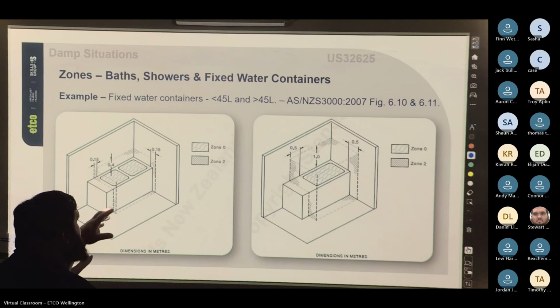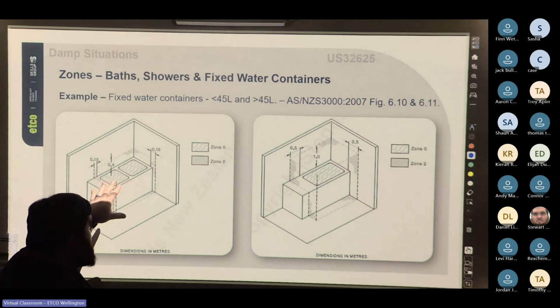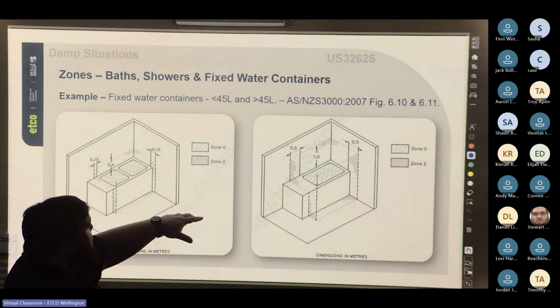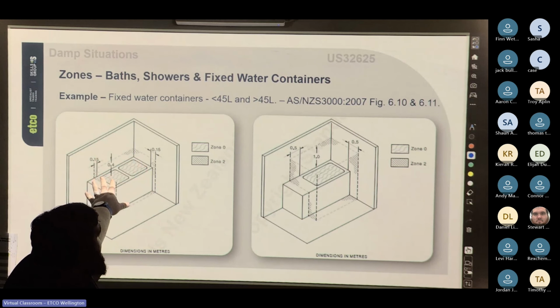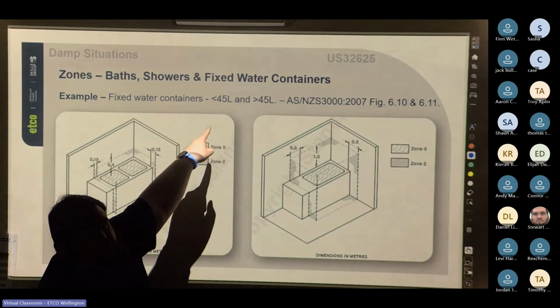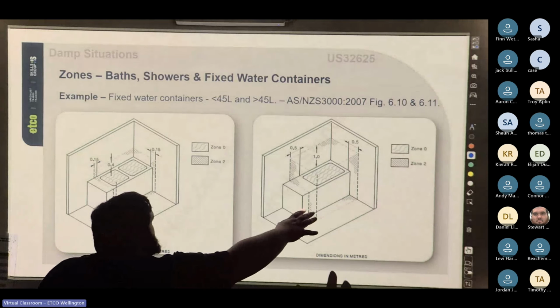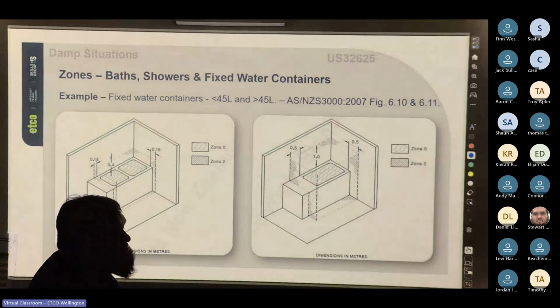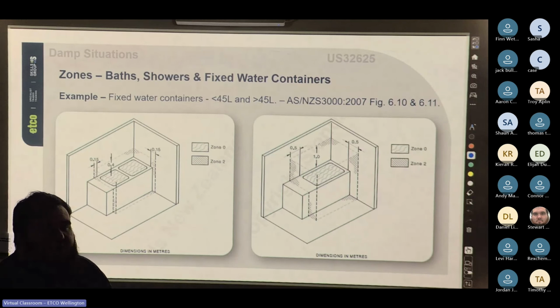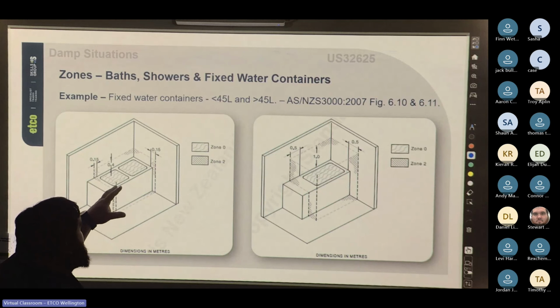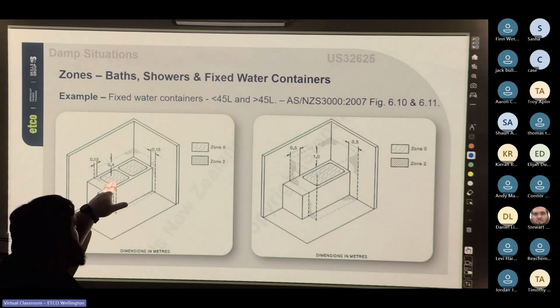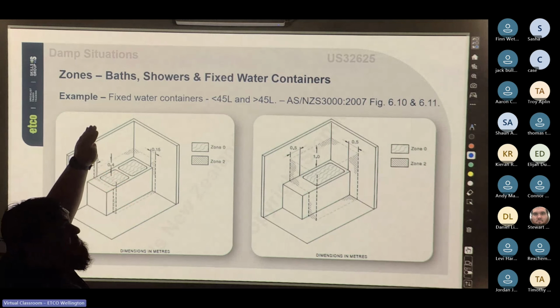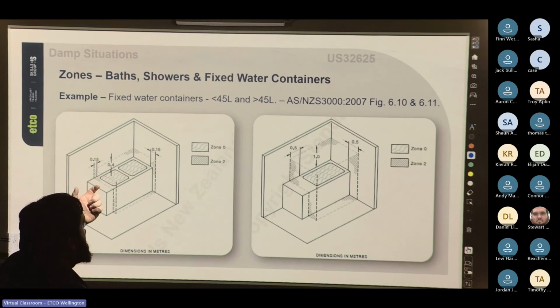So yeah, the difference between these two, and it's listed: the fixed water container on the left is less than 45 litres. The fixed water container on the right is more than 45 litres. So that 45 litre mark is where the legal measurements change. So below 45 litres, zone 0 is the water. Zone 1 is still directly above the water, but zone 2 is only 0.15 metres and 0.4 metres above. So zone 1 is the surface of the water up to 0.4 metres.